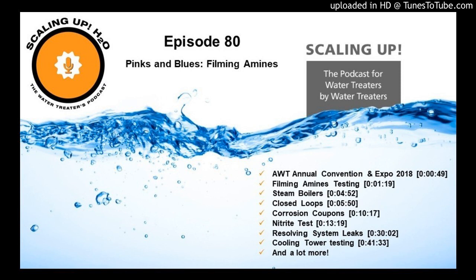The only thing we were doing was replacing our current inhibitors, our current program, with this new Filming Amine program. And now we're at the point where we flushed the system. We went ahead and got everything out of the system. We did this online, and we tested a couple of things: conductivity, pH, azole, nitrite, alkalinity. We tested all those.